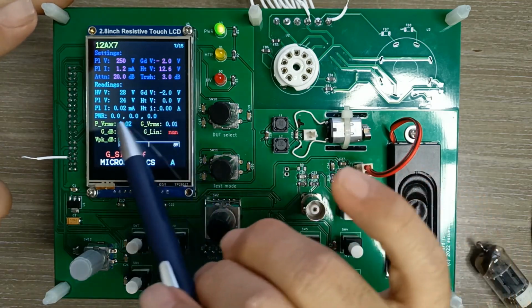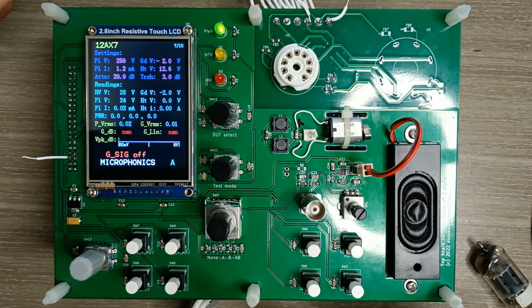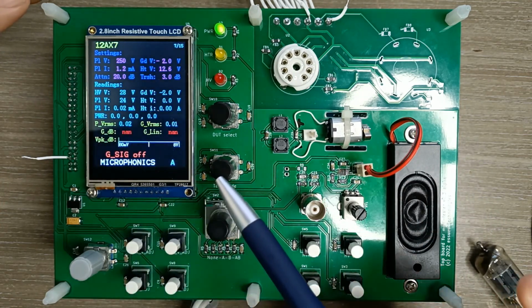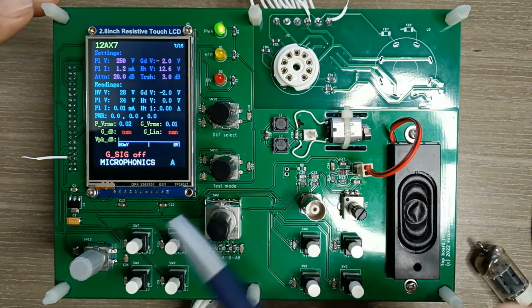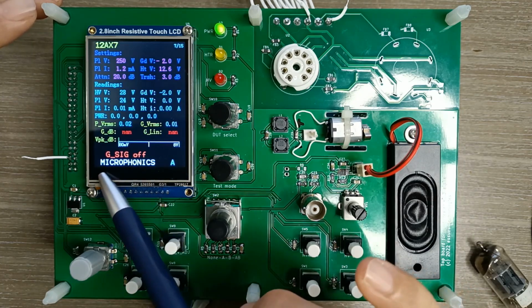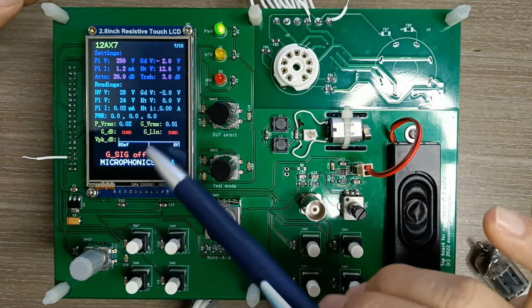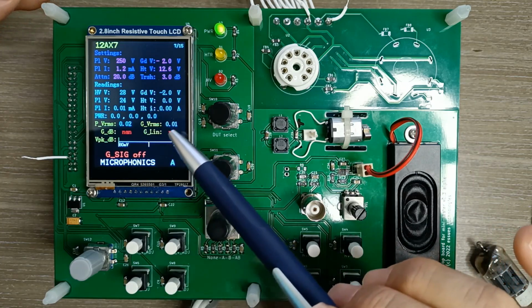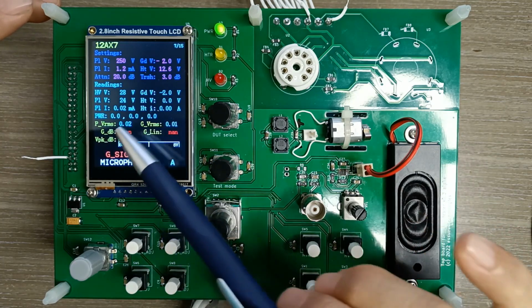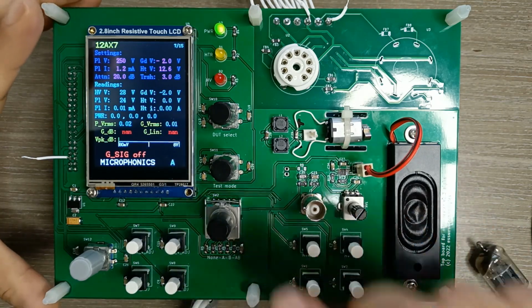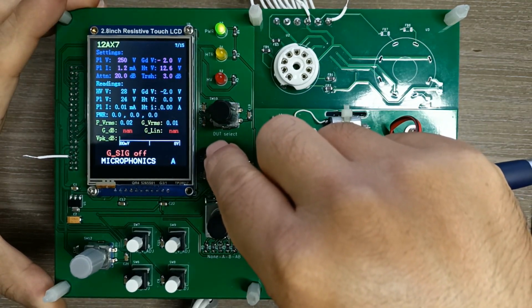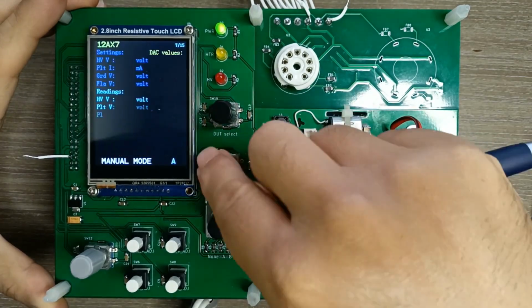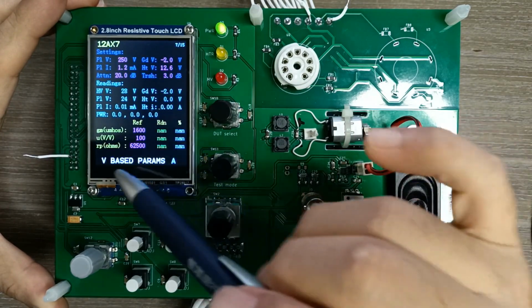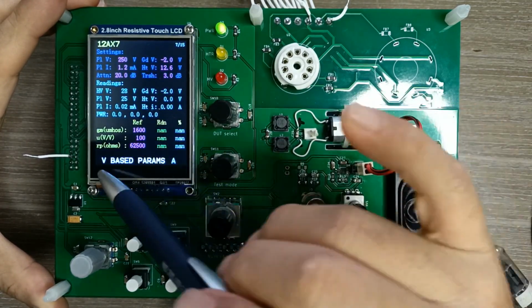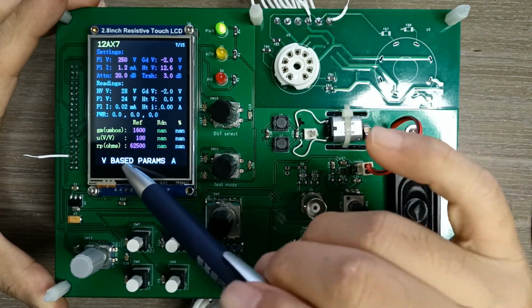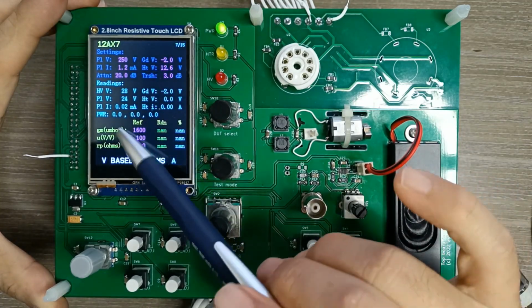Okay, and the third block is the test result block. The parameters shown here vary by different test modes. So currently we are under microphonics test mode, as indicated at the bottom row. And we see there's a plate signal VRMS, a gain VRMS, the gain in dB, and the linear gain. And we have the sound level meter here. So you can see this block will give you different ratings with different test modes. So here we are under voltage based parameter extraction mode. So it will give us different readings like GM, mu, and RP.